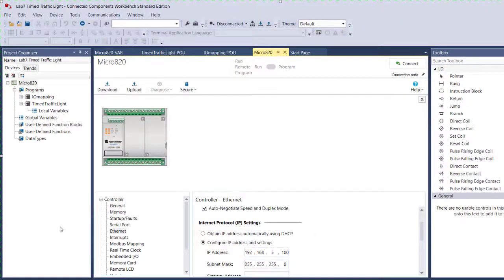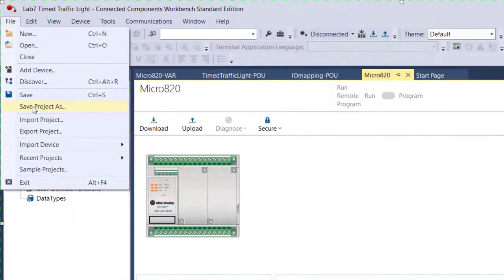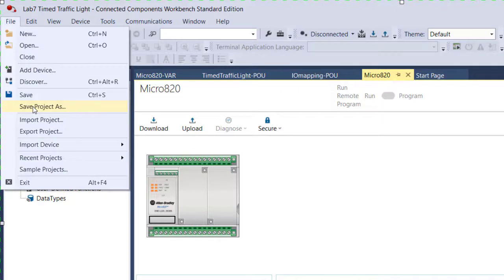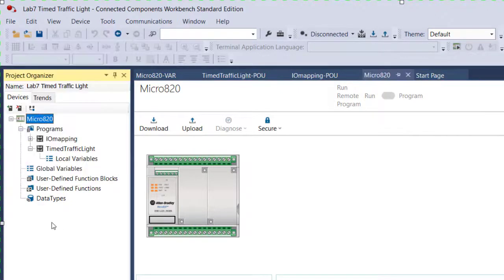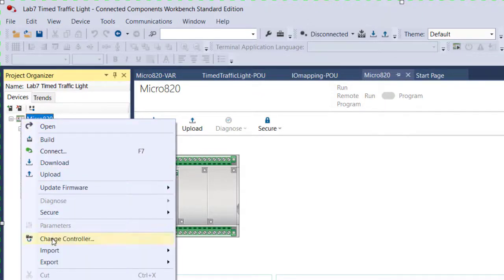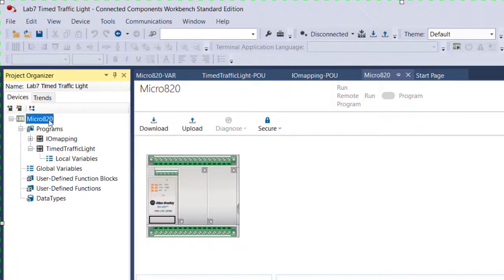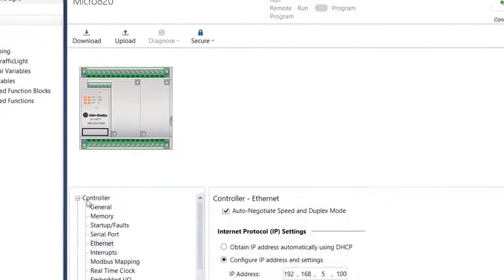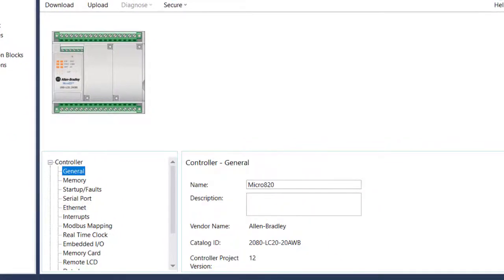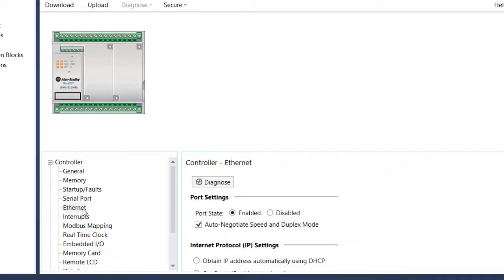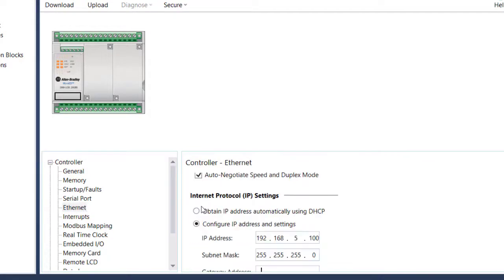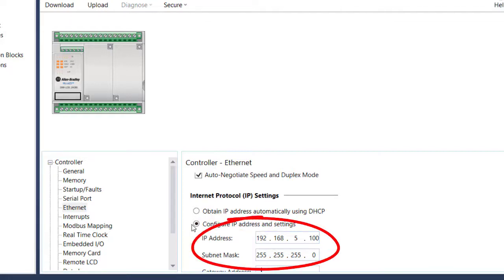Here I am in Connected Components Workbench. All I did was open the day 20 homework assignment and did a save project as to my lab 7 folder and called it the lab 7 project instead. Once I did that, I right clicked on the controller and had to change the controller, because it was originally set up for the Micro 850 simulated controller. So we needed to change that controller to this Micro 820. You can see here in the General tab the part number for that controller. And when we go to the Ethernet tab, you'll notice that we have to select to configure the IP address ourselves rather than to obtain it automatically. The IP address that we've configured is 192.168.5.100. So you'll need to make sure to configure your Micro 820 controller in CCW to this Ethernet address, so that you don't overwrite it on the actual PLC.